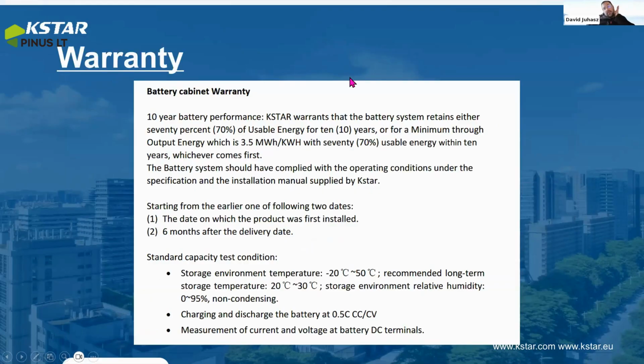Regarding the battery cabinet, we have a 10-year performance warranty. We warrant that the battery system retains either 70% of usable energy for 10 years or a minimum throughput energy of 3.5 megawatt hours. That means it's the maximum discharge energy during the lifetime. And we ensure that the state of health is 70% at this level. The battery system should comply with the operating conditions under the specification and the installation manual supplied by us. And the starting dates are the same.